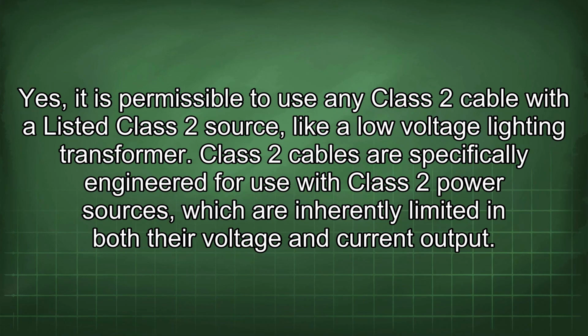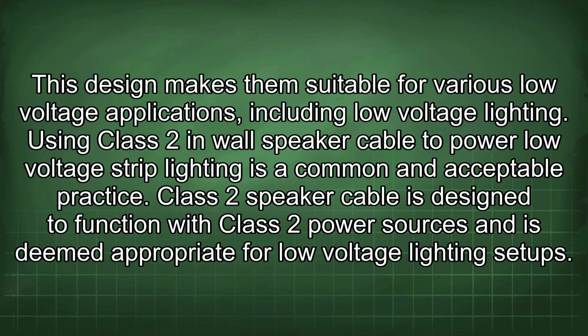Yes, it is permissible to use any Class 2 cable with a listed Class 2 source, like a low-voltage lighting transformer. Class 2 cables are specifically engineered for use with Class 2 power sources, which are inherently limited in both their voltage and current output.